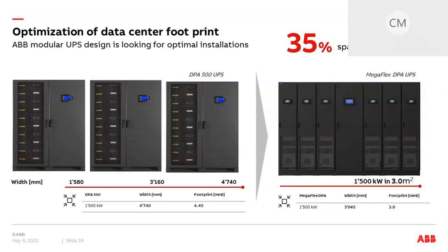One of our targets is to optimize and support the data center footprint. Therefore, high power density is an important value, not only for the data center customers, but for us as well. We look for solutions to optimize these precious spaces without compromising the power capacity and the performance. The DPA architecture and the smart UPS design offer a very compact footprint for large infrastructures, allowing more effective use of the space. The system can be connected from the top or bottom, installed against the wall or side to side, offering different installation layouts.